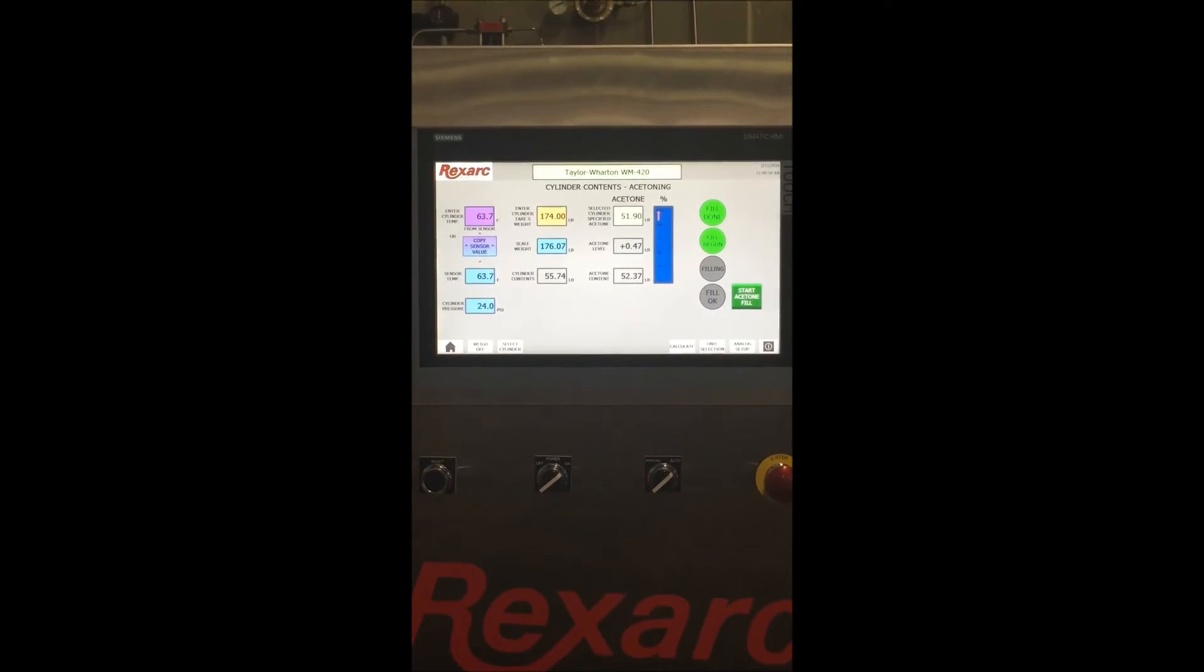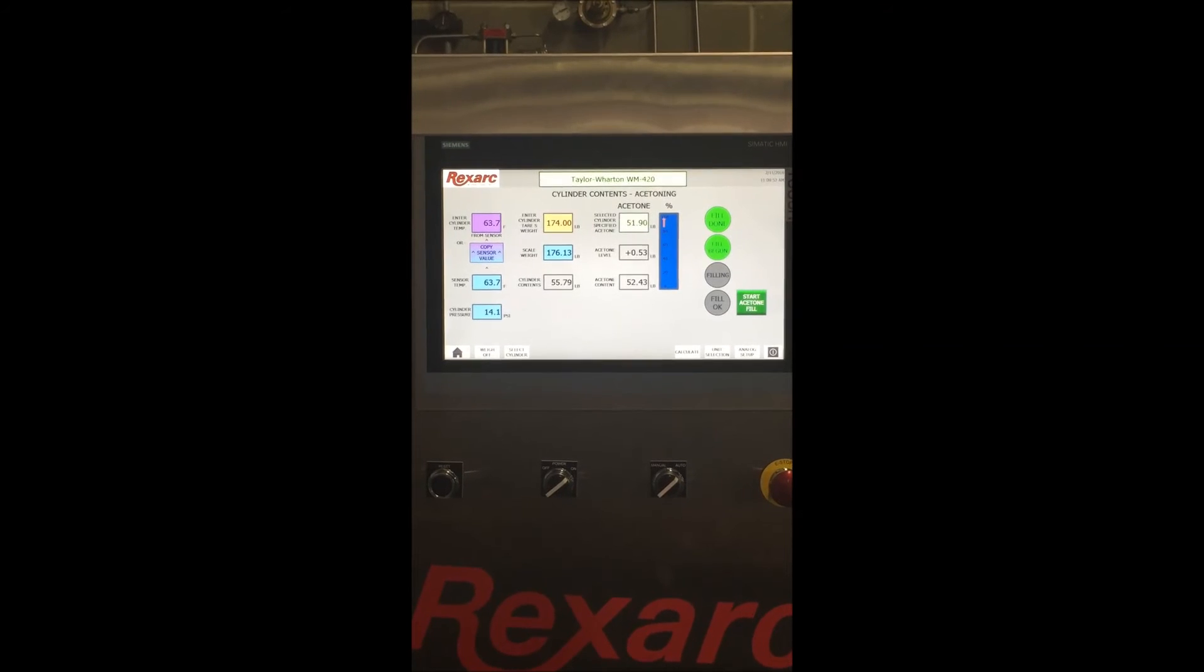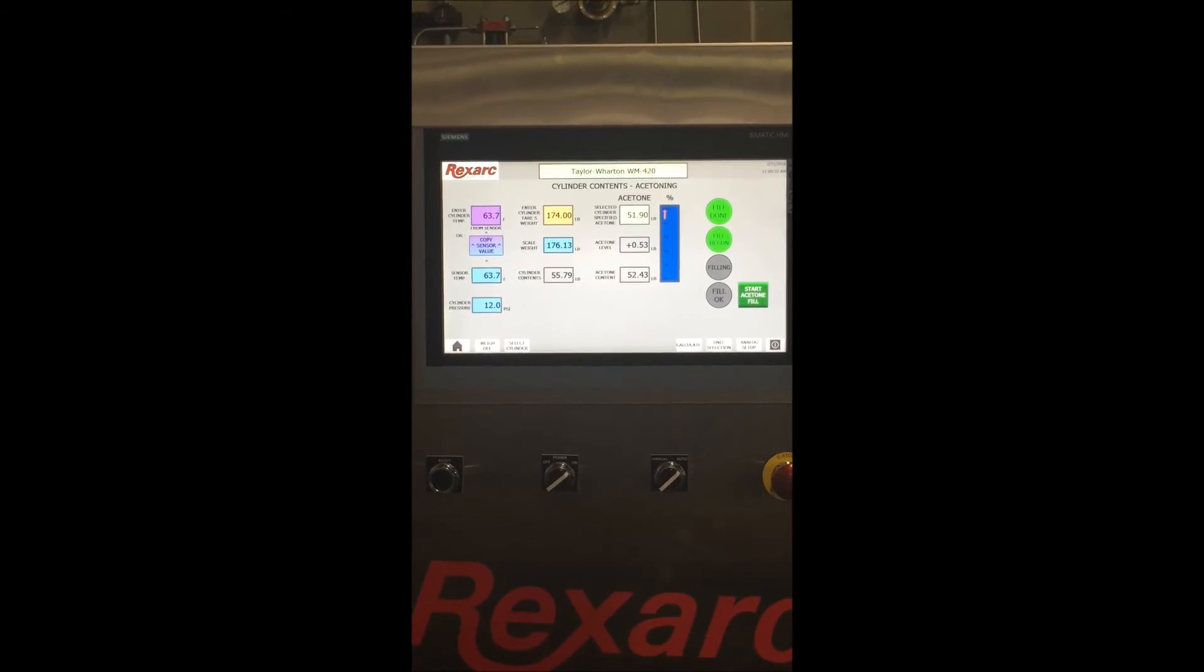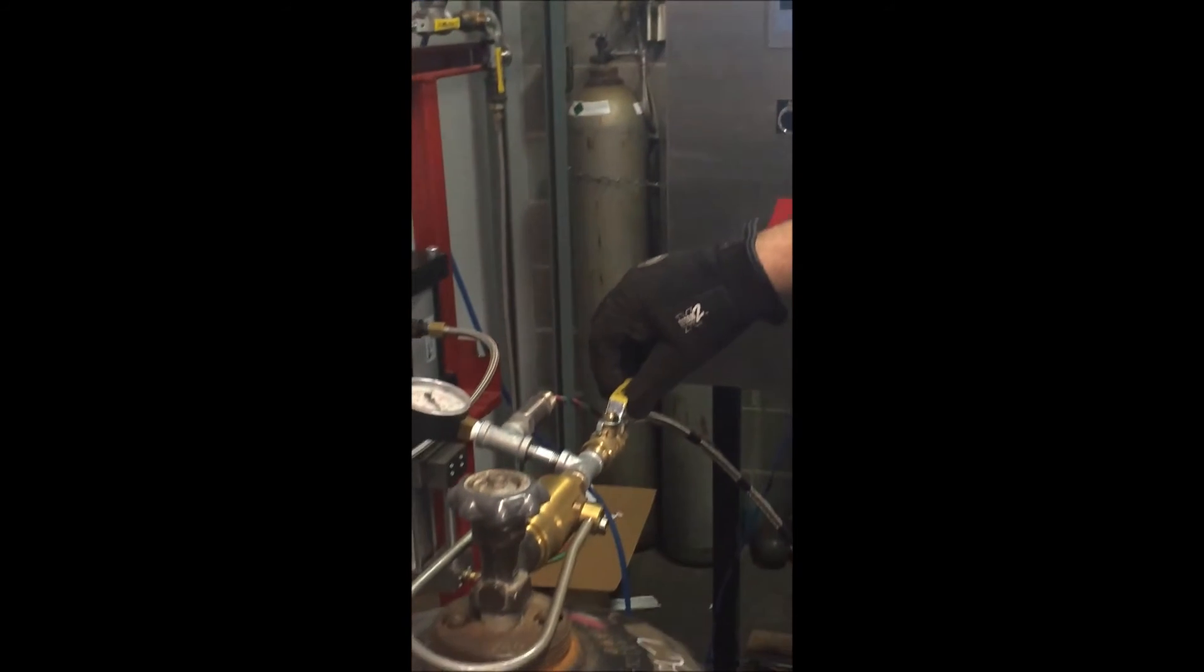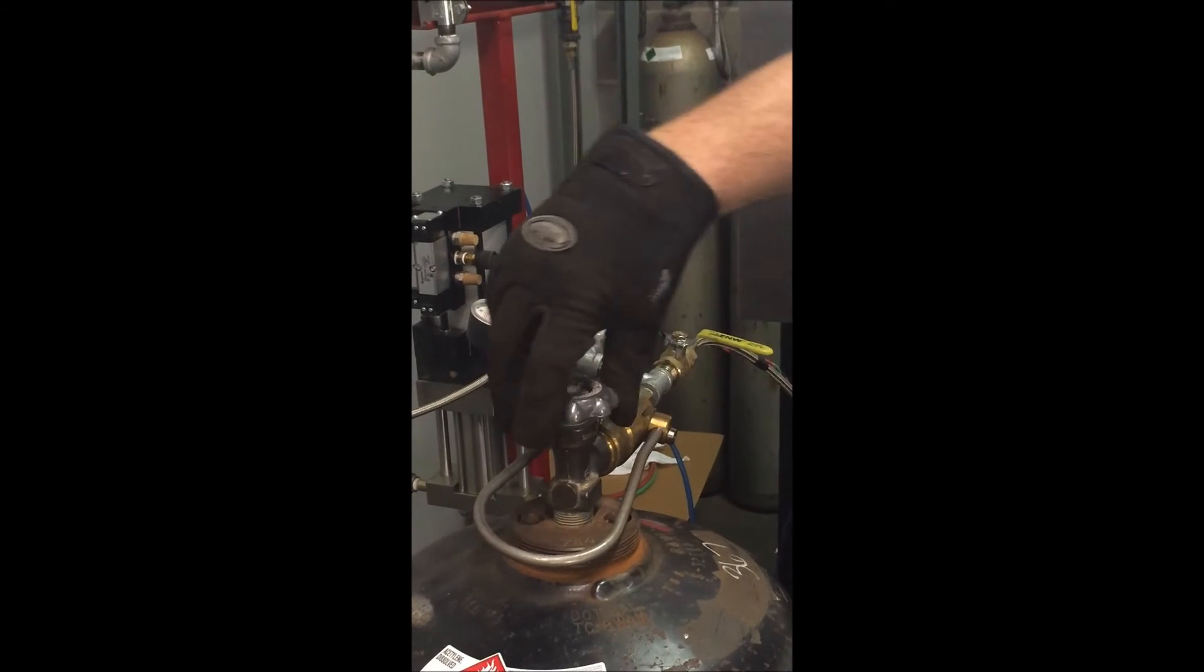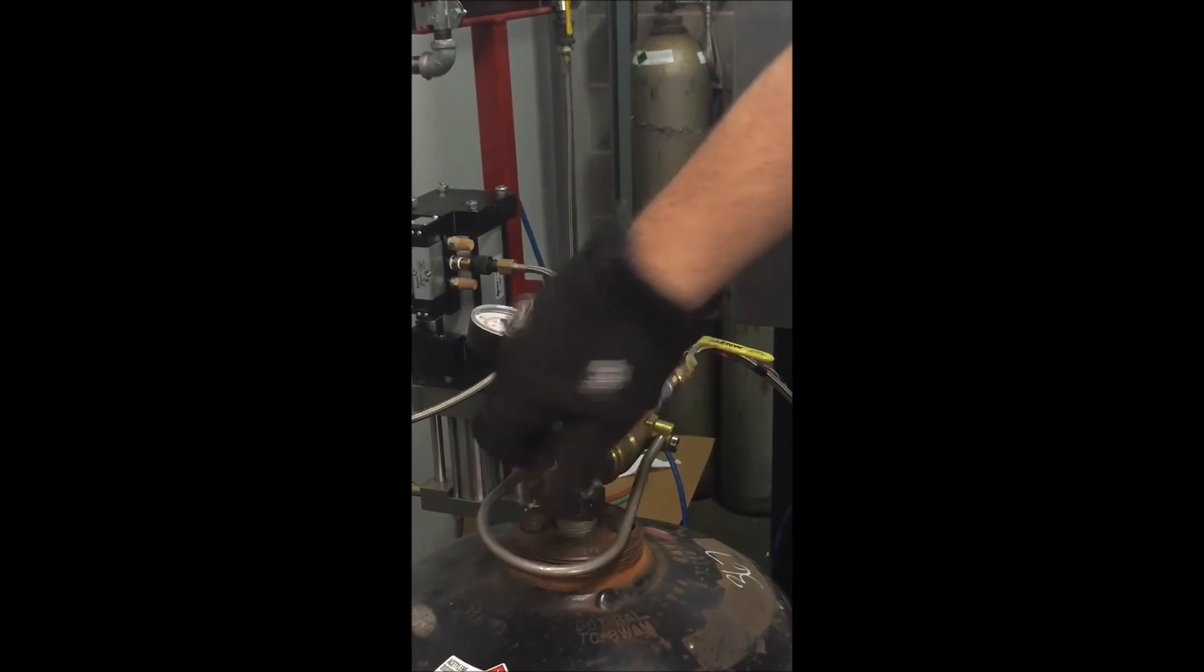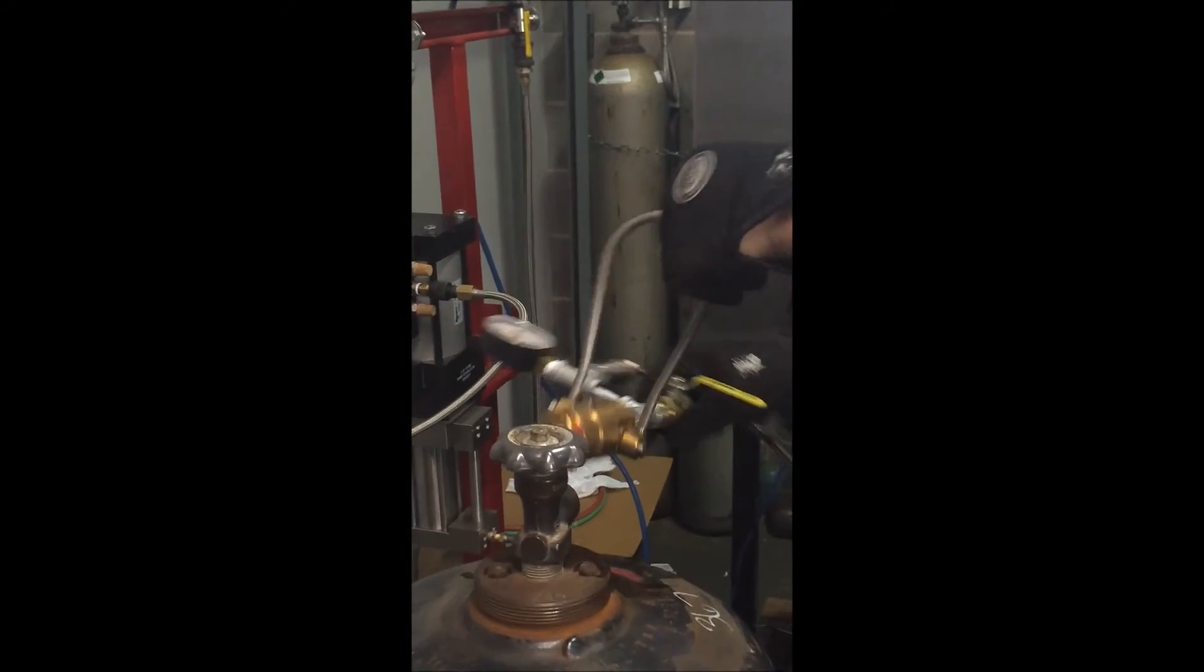Once the panel has calculated the correct amount of acetone is now in the cylinder, it will automatically shut the supply to your acetylene cylinder off. At that point you can close your hand valve on the acetone piping, close your cylinder valve, and disconnect your line.